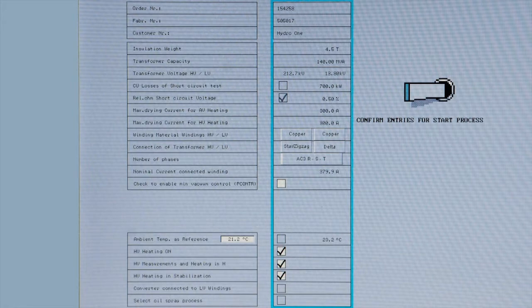HV heating in the stabilization stage. If HV heating is preferred in the stabilization phase, the HV measurement will be done after each heating break. The recommendation is to use all HV heating modes only when there is a big difference in current density between the windings, or the design will generate an asymmetric heating. The HV measurement takes some time, and the oil circulation system normally ensures that the temperature is relatively evenly distributed.